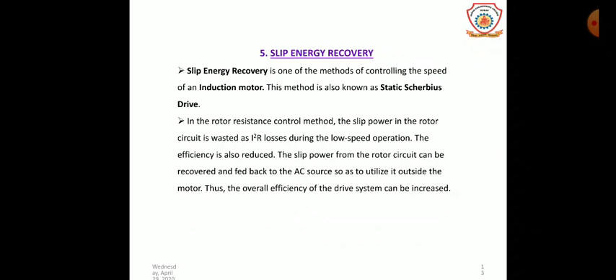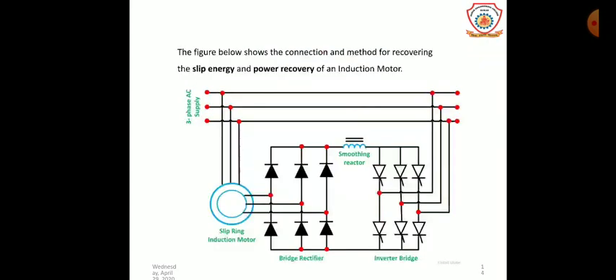The slip energy recovery method is one of the methods of controlling the speed of an induction motor. In the rotor resistance control method, slip power in the rotor circuit is wasted as I²R losses during low speed operation, reducing efficiency. In the slip energy recovery method, the slip power from the rotor circuit can be recovered and fed back to the AC source so as to utilize it outside the motor, increasing the overall efficiency of the drive system.